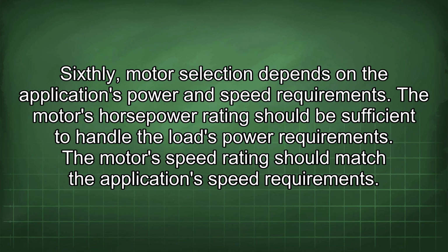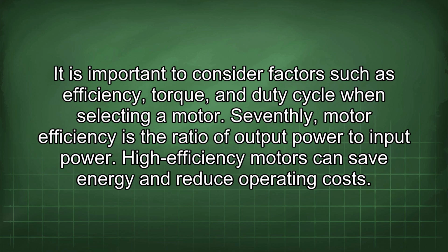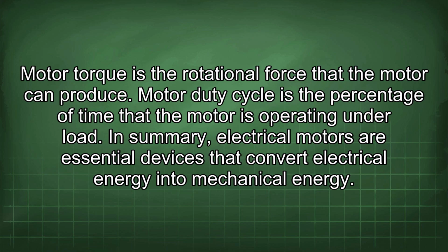The motor's horsepower rating should be sufficient to handle the load's power requirements. The motor's speed rating should match the application's speed requirements. It is important to consider factors such as efficiency, torque, and duty cycle when selecting a motor. Seventhly, motor efficiency is the ratio of output power to input power. High-efficiency motors can save energy and reduce operating costs. Motor torque is the rotational force that the motor can produce. Motor duty cycle is the percentage of time that the motor is operating under load.